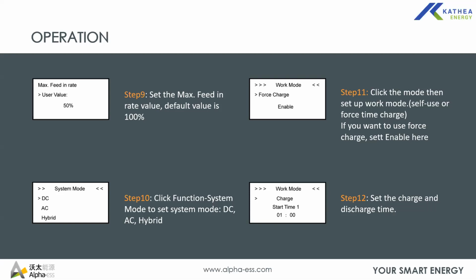So if you access any of the settings, you are prompted for force charge. Force charge is basically, if you enable it, charging from the grid. If you just enable the force charge and you do not set the times when you want to charge your batteries, the system will not charge from the grid. So when you enable force charge, it will give you more options to set your charge start time 1, end time 1, start time 2, and end time 2.